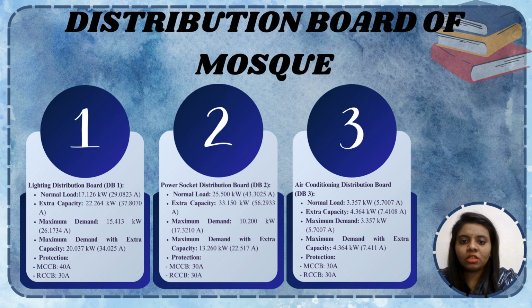It can handle a load of 25.5 kilowatt and 43.3025 ampere, increasing to 33.150 kilowatt and 56.2933 ampere with the extra capacity. The maximum demand is 10.2 kilowatt and 17.3210 ampere, rising to 13.260 kilowatt and 22.517 ampere. This DB is protected by a 30 ampere MCCB and RCCB.